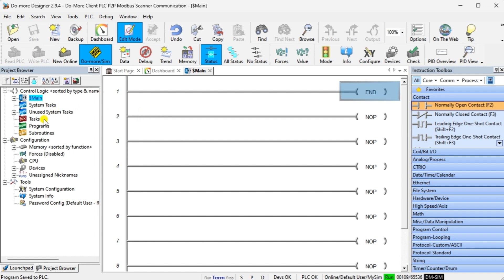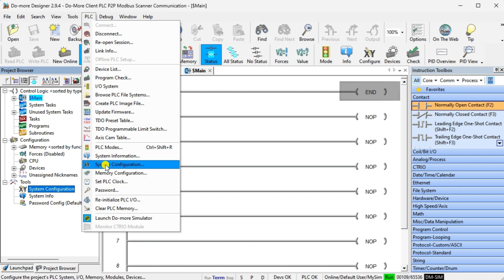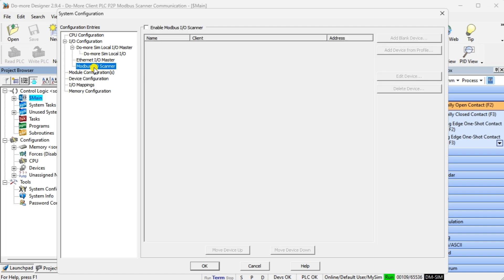Select System Configuration from the main menu PLC or under the Tools menu in the Project Browser. The System Configuration window will now be displayed, showing you the IP address. The IP address will be the same as the computer running the PLC simulator. Select Modbus IO Scanner under the IO Configuration menu on the left side. Select Enable Modbus IO Scanner — this will allow us to use the scanner.